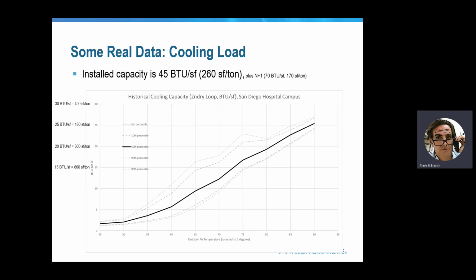So here's a hospital. I come from Kaiser. Everybody wants to see hospital data. This is the hospital chiller system. The hospital does see some higher loads when we got up over 25 BTU per square foot in the 90-degree hours. But the sizing also went up here. In this case, the engineer sized the chillers. There are 2 chillers at 45 BTU per square foot. And then, of course, we have an N+1 chiller. So the total plant capacity is 70 BTU per square foot. And we're not really sure if we've fired the second chiller, but I don't think we've ever actually needed the second chiller, right?